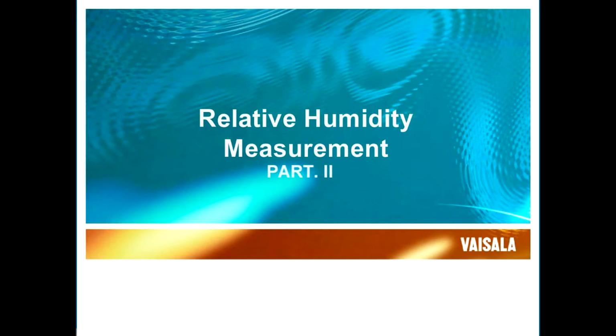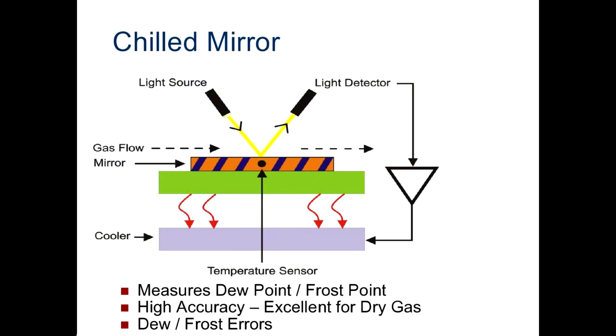The next humidity measurement device is what's called a chilled mirror hygrometer. And just as the name suggests, inside such an instrument, there is a little mirror that reflects light. This mirror is electronically cooled. And by looking for a change in its reflective properties, we can determine where dew first forms. And by measuring that temperature, we know the dew point of the air or the gas that's going across the mirror. Now, one can get very high accuracy measurements with a dew point hygrometer, but they do have maintenance issues associated with them.